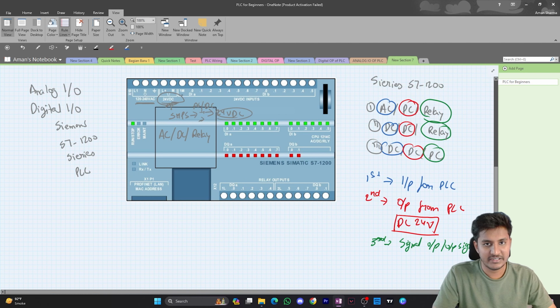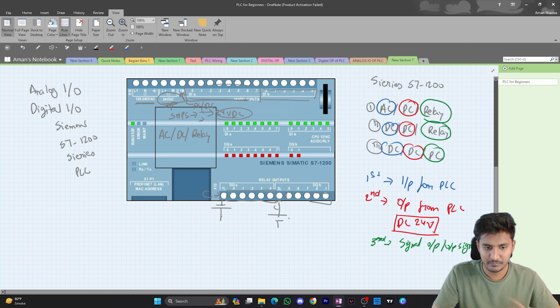We have a common, this one is our common, and these are the ports. You can make two commons if there is one more option available. Here you have relay output, and here you have to make it sinking or sourcing type. So this is common, and these are our ports, and this is also another common. So you can have one sinking output here and one sourcing output here, depending on your application.